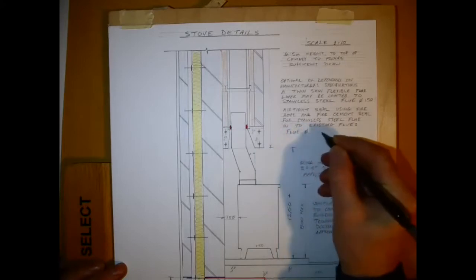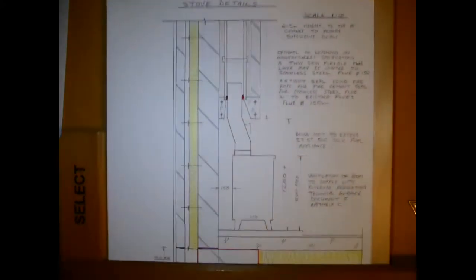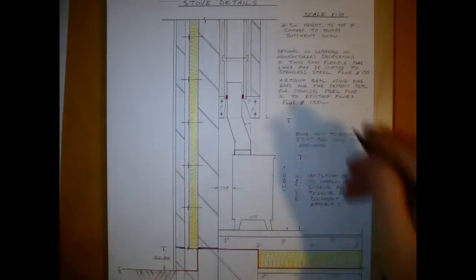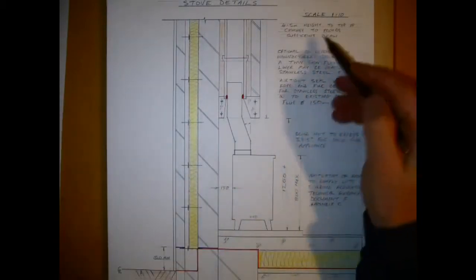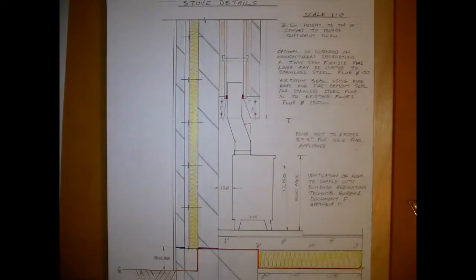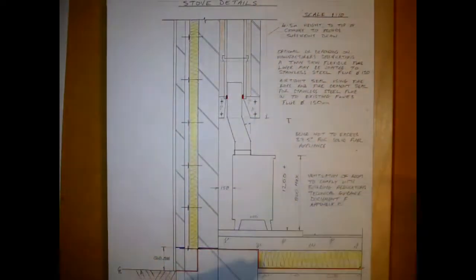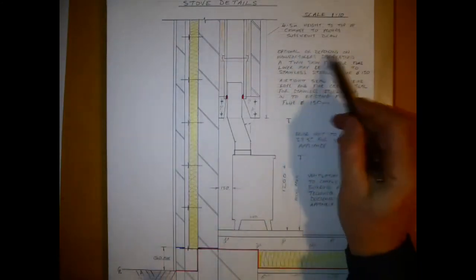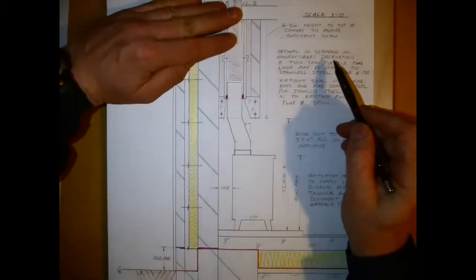And the way the flue would be jointed, different manufacturers will have different methods of that, but the likes of fire rope, fire cement, possibly used to make a tight seal around the flue gathering and down into the flue gathering, which I haven't highlighted here, but it would have to be airtight. And maybe even the use of the twin skinned flue would be another option as well.